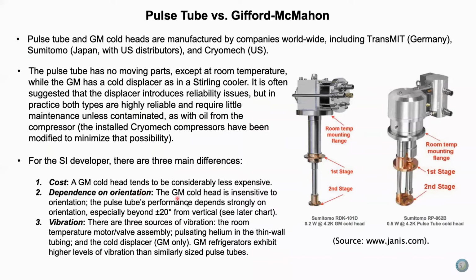Now, for the SI developer, there are three main differences between pulse tubes and GMs. The first one is cost. The GM tends to be quite a bit less expensive. Second is dependence on orientation. The GM is insensitive to orientation or tilt. Remember, the cryostat has to tilt up to 20 degrees in either direction from the vertical. The GM doesn't care about that. The pulse tube does. There is a fairly strong dependence on deviations from vertical.